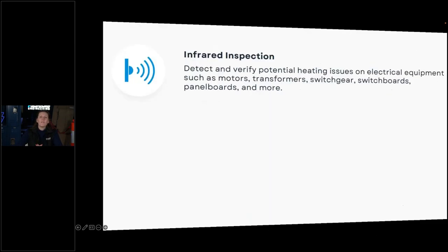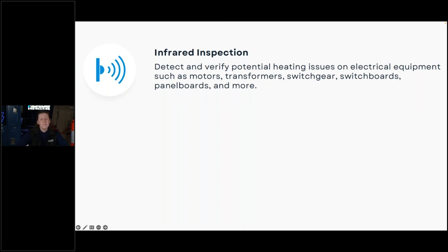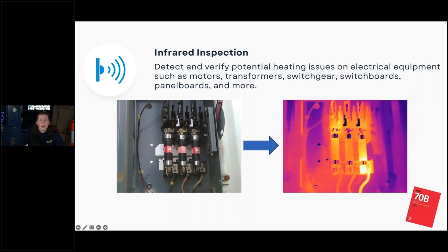The purpose of these scans, as required by 70B and NETA, is to help detect and verify potential heating issues on your equipment - motors, transformers, switchgear, switchboards, panel boards, disconnect switches, even control cabinets. We want to see if there are hotspots. Sometimes just looking at it with the naked eye, you can tell something's wrong - if it's glowing red, for example, you don't need an infrared camera to see that there's something wrong. But a lot of times it's more subtle and nuanced than that, so you do need an actual infrared camera to see those hot spots. It'll pick up things that are not visible to us; our eyes don't detect it that way.